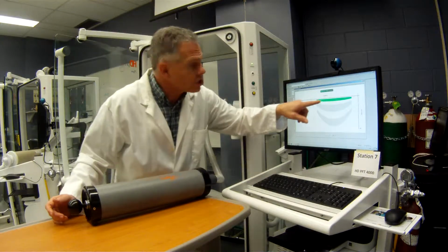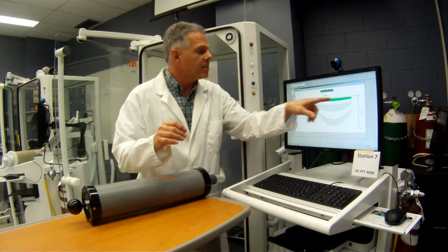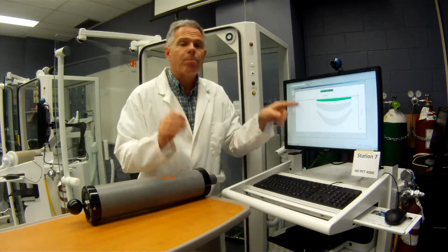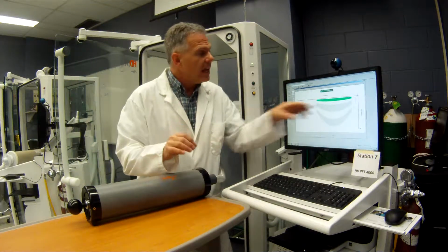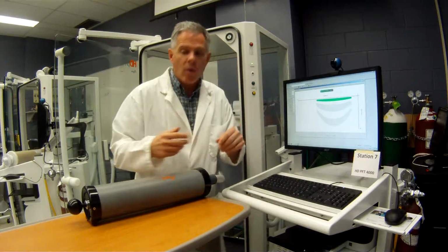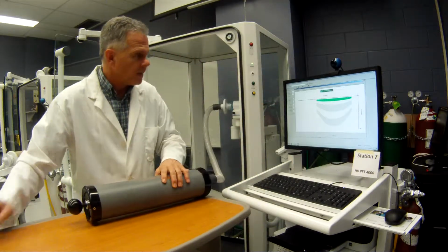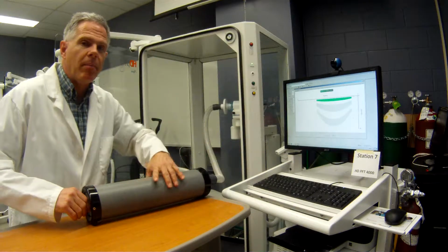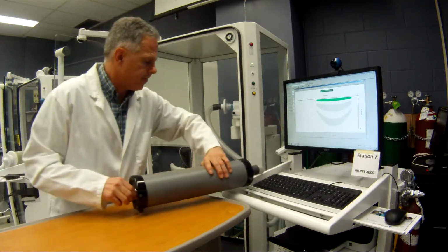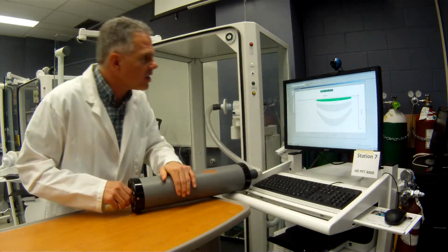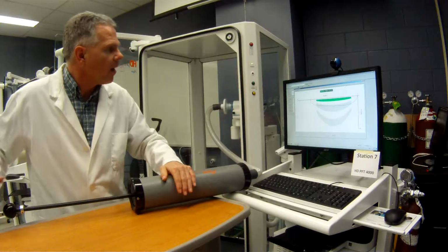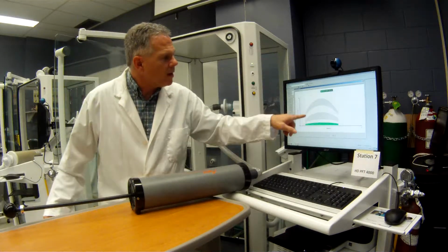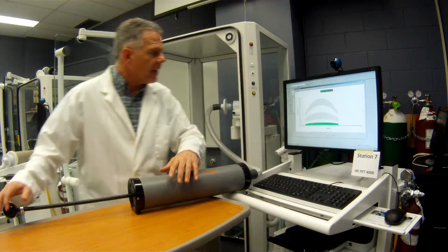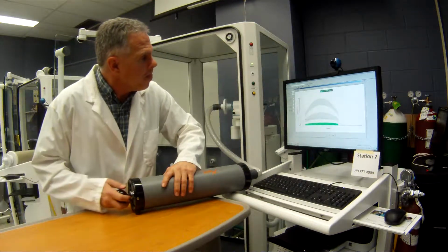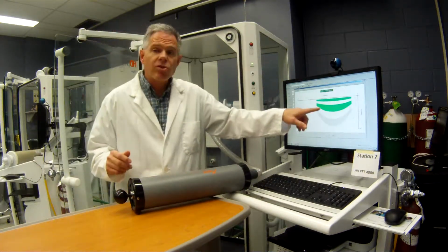When it comes back and it shows me green, that means it's measuring 3 liters at the specific flow rate that I want. If we don't match that flow rate, it'll ignore the procedure. All right, so let's now get a little bit faster flow rate. Set that there so you can see me. All right, so we've met that one on the inspiratory, now it's looking for the expiratory stroke. So we've met that. That turned green.